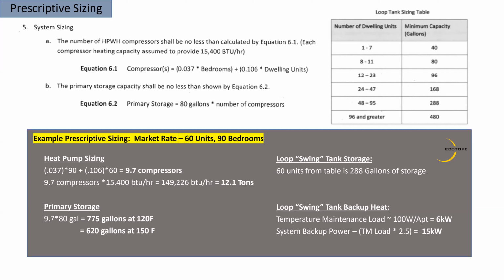And then the loop swing tank storage. There's a table in the sizing guidelines. So in this example, we've got 60 units, and that results in 288 gallons of storage. That'll allow you a 5-hour draw, a 5-hour no-draw period. And that's how that gets sized.